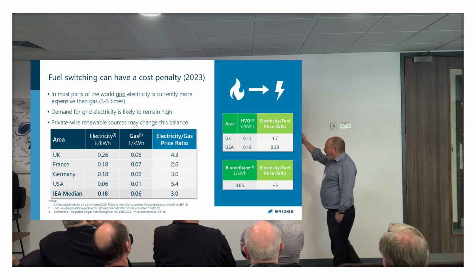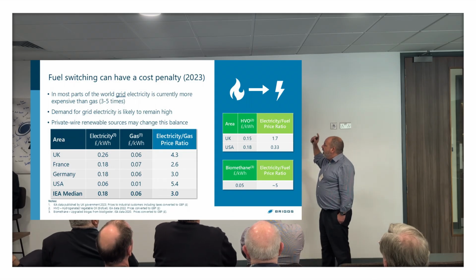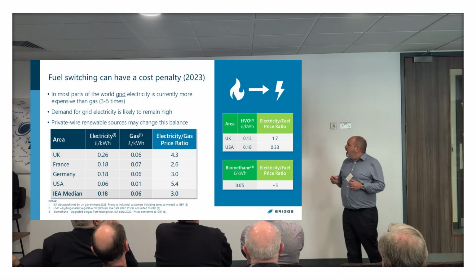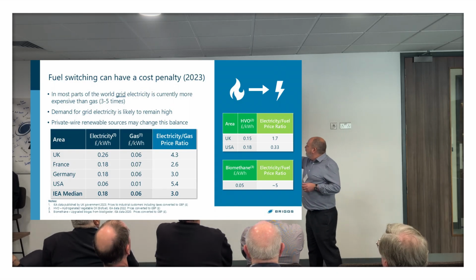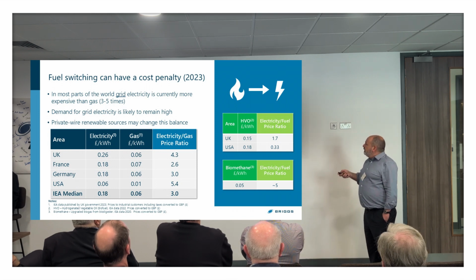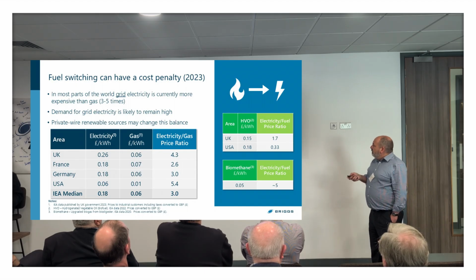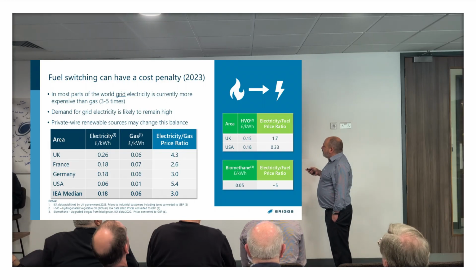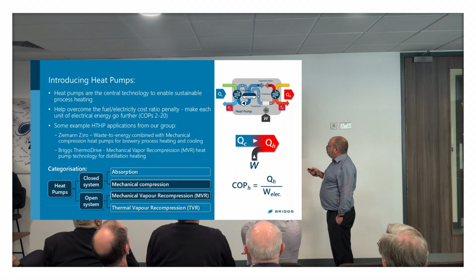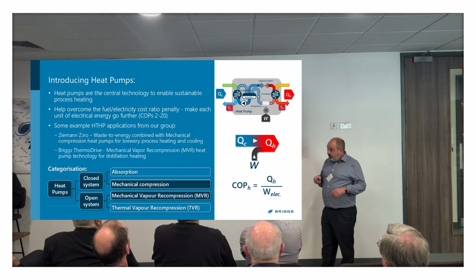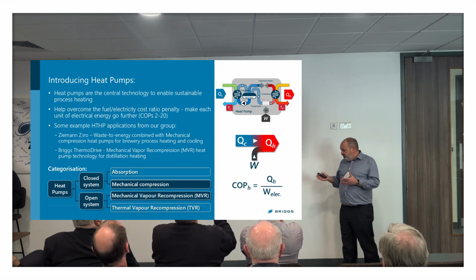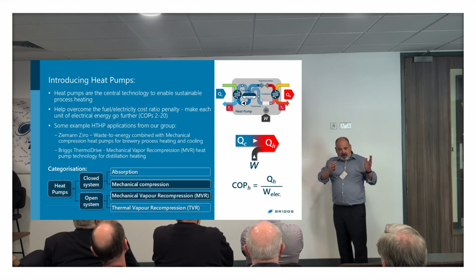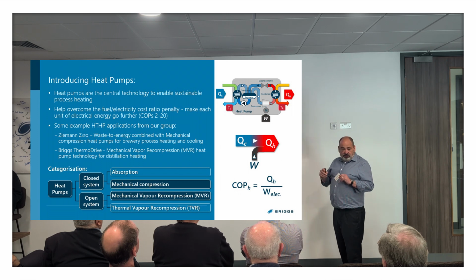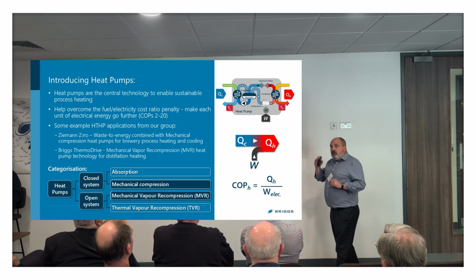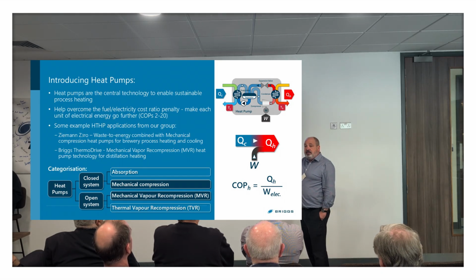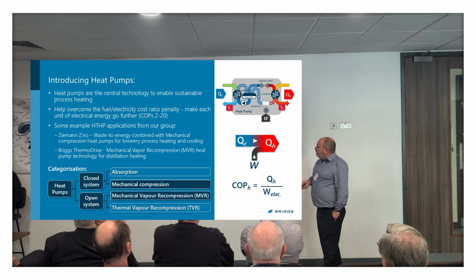Now, we talked about private wire, and saw that example in China. Local sources of renewable electricity might change that balance. This is the cost ratio for electricity to gas, but it's very similar for green oils, etc. So we can potentially decarbonise in the long term by changing to electricity. We get an efficiency benefit by changing our boilers over to electric boilers. But to overcome the cost disadvantage at the moment, we really need to make the electricity work for us. And that's where the application of heat pumps comes in.